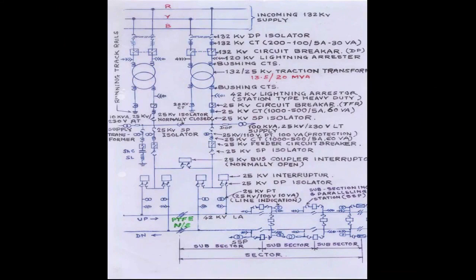When we talk about two impedances in parallel, and that too moving, not fixed, a moving impedance comes into my transmission line network. That is your 25 kV line network. So if you have a moving impedance coming into the network, the relay should be aware of what is happening.